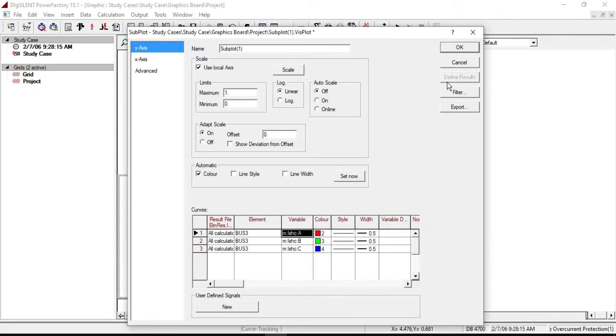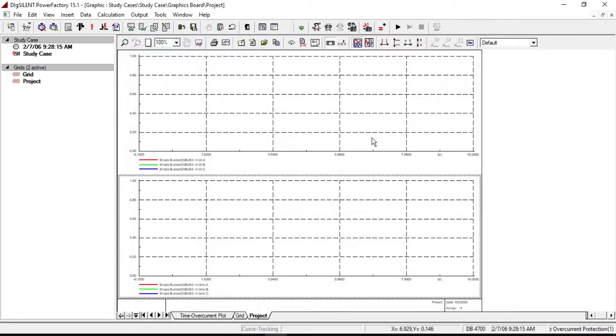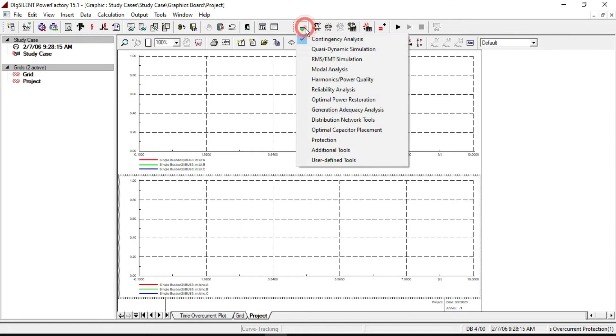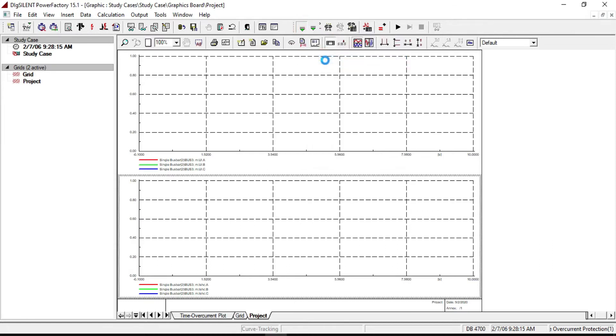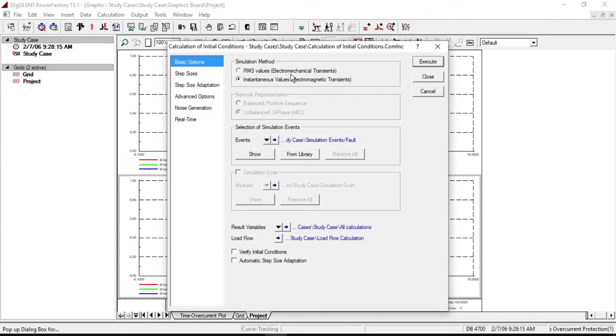Now we need to execute the voltage and short circuit current waveform for both normal operating and fault condition. From the Change Toolbox icon, select RMS/EMT simulation. Then calculate initial conditions and make sure that the simulation method is on instantaneous values. If you select RMS values, you will see a straight line. Click on Execute.